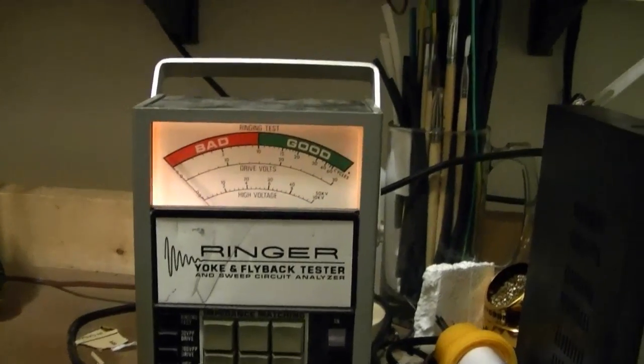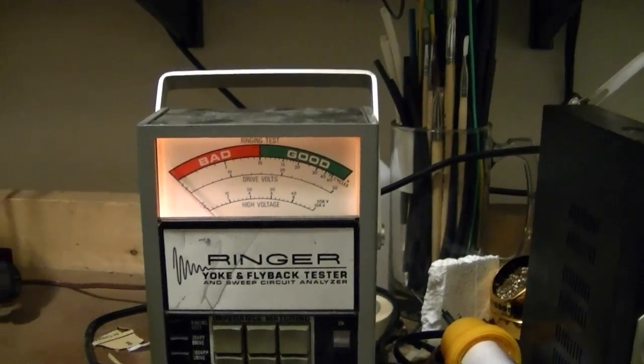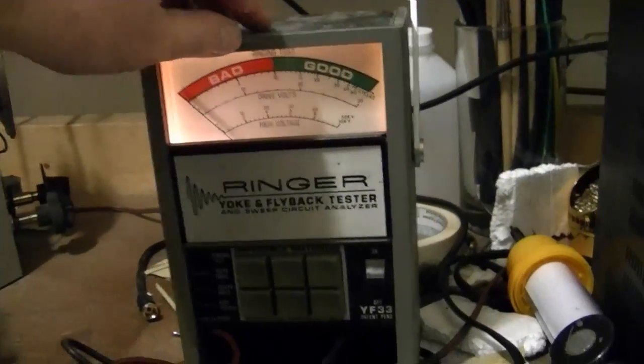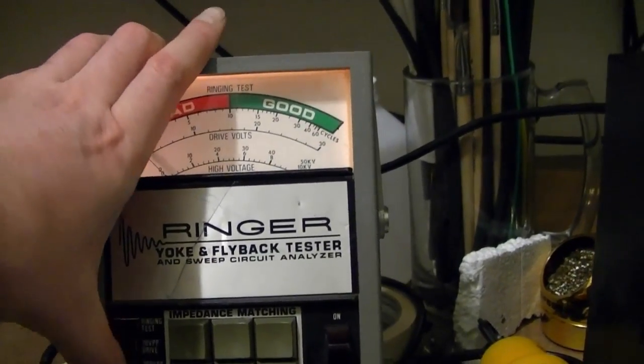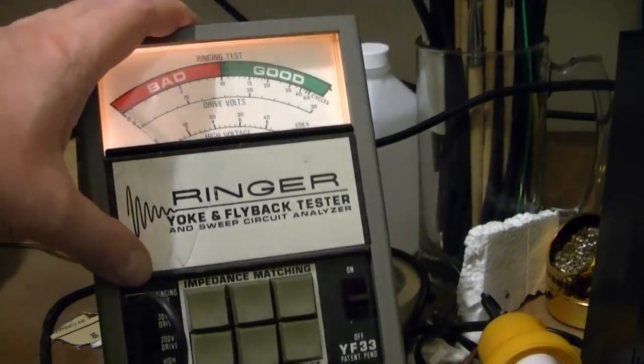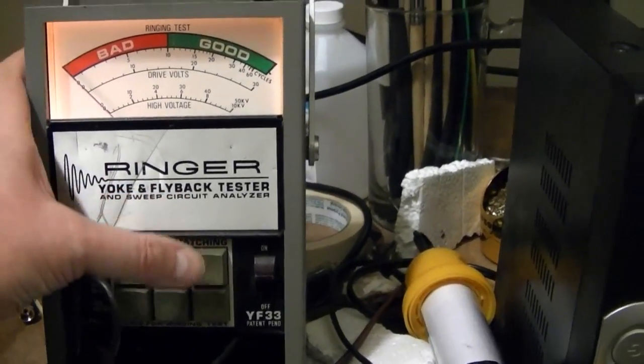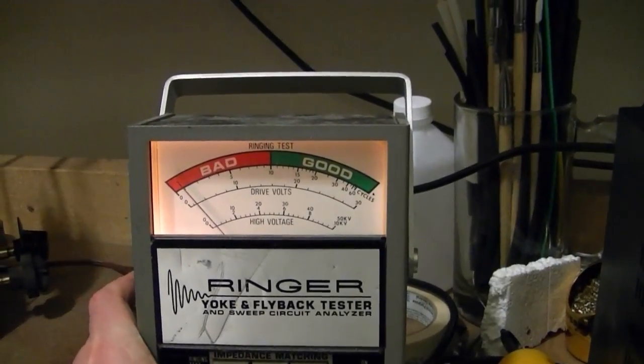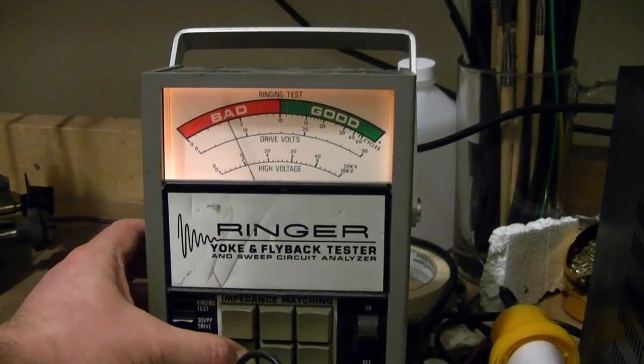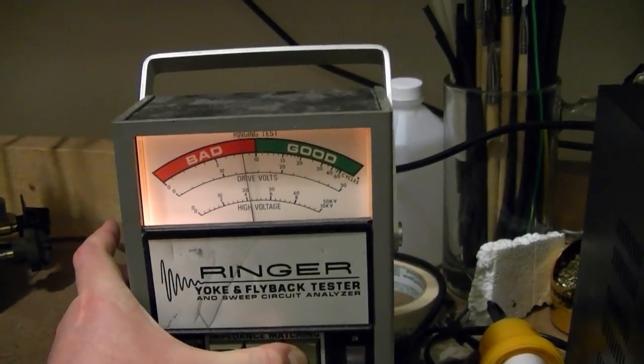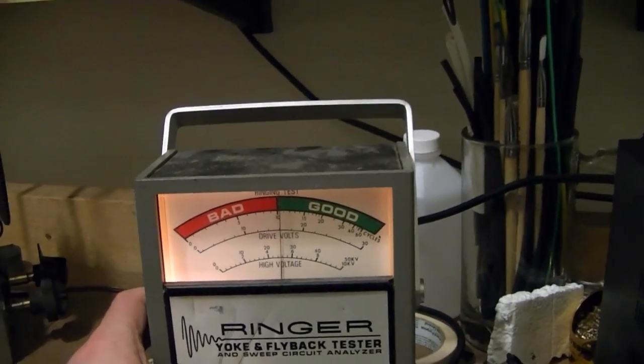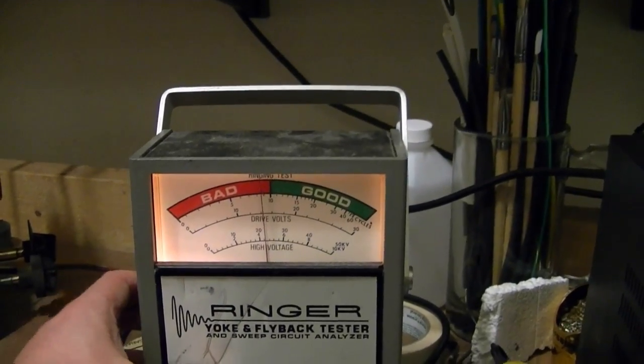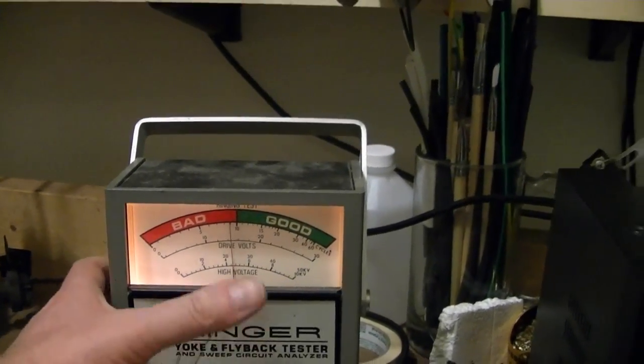Okay, the way the Sencore YF33 works is very similar to the VA62 in that there's a meter, ringing test, bad, good, select ringing test. It can do some other stuff too. We're just going to do the ringing test. And you have 6 push buttons, whereas the other one has a 6 position rotary switch. Here you've got 6 push buttons to find the impedance match, and you just go through, try each button, and whichever one gives you the highest reading, that's what you go with. About up to 8. And then we go, about 10. That's what we got with the VA62 as well. So I get about 10 rings on both. So I think that's a pretty good indication that both devices are working correctly.